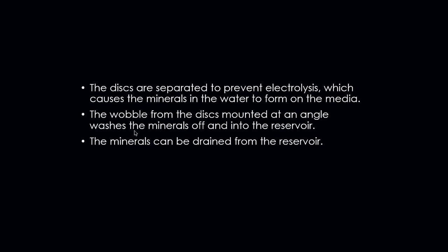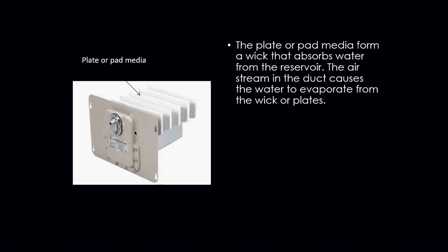Okay, we cannot just let the water sit in there for an entire year and do absolutely nothing with it. If a humidifier is going to be shut down, say for the summer months, that reservoir needs to be drained, the disc needs to be removed and thrown out, and maybe put a brand new one in, shut the water off to it, and render it nonfunctional until that homeowner or that person is ready to use it again. Okay, the minerals can be drained from the reservoir. However, the more minerals and deposit we have, sometimes you will run into the drain line being plugged up on them.